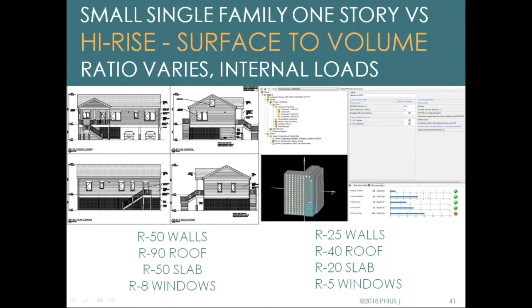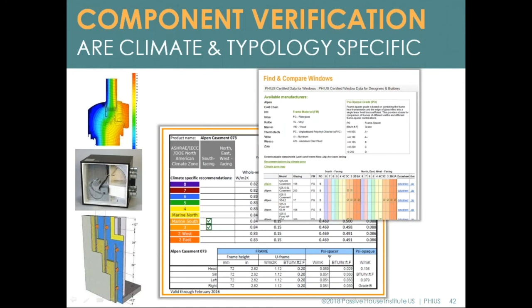Components are climate specific, and so are mechanical systems, ventilation systems, heat recovery, efficiency of the motor, enthalpy, humidity recovery - all these things matter. For components, climate specific decisions include where the airtight layer goes, so we can have only one and not redundant layers on the inside and outside. We can place it in the right spot in the wall. It can be a vapor control layer, a vapor retarder, and give us a durable, well-performing wall assembly. We have certifications for these climate-specific and typology-specific components now under PHIUS Plus.